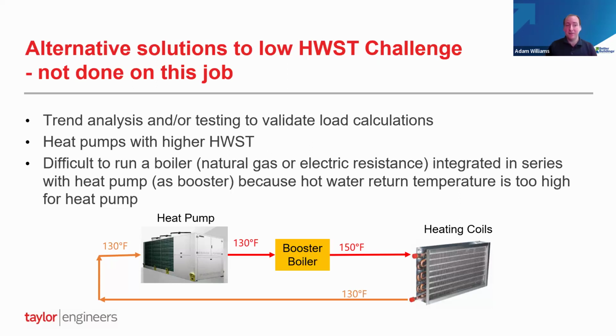So other things you can do, there are heat pumps that work with higher hot water supply temperature. There are heat pumps that have CO2 refrigerant that can provide higher hot water supply temperature. Our experience is that those are really expensive, they become cost prohibitive, and it may make more sense to do the work down in the space than use those heat pumps. Also, those units are a lot less efficient. But that is an option.